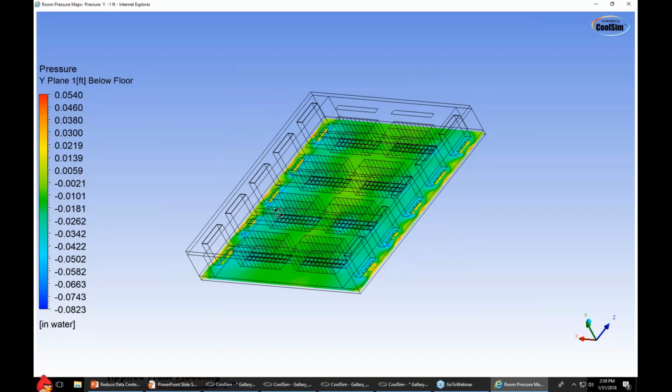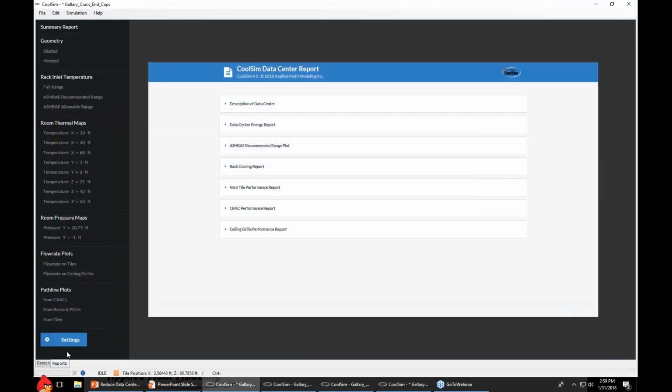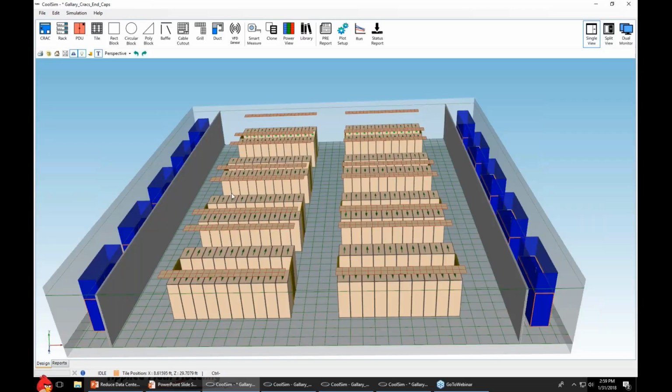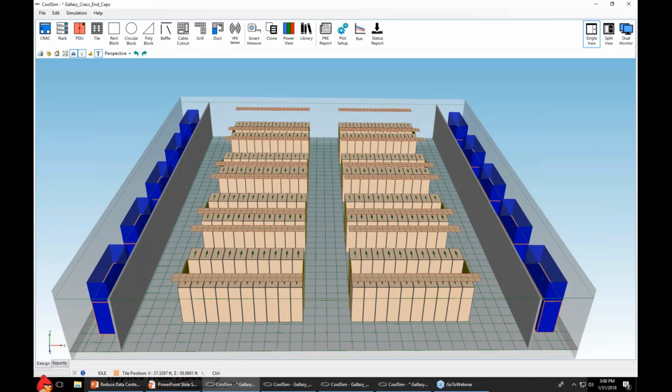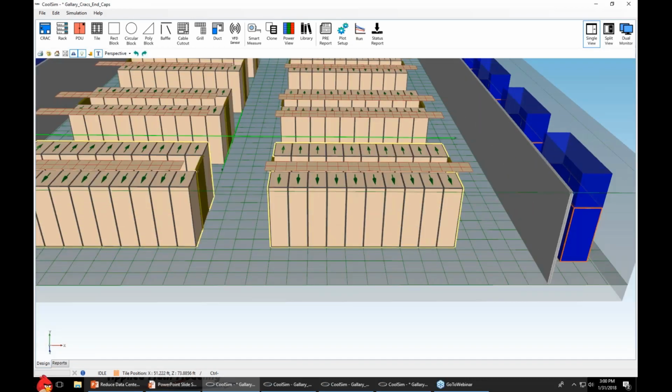Okay, how do you measure the airflow of each rack? It's difficult to measure the airflow of each rack. None of us really know. This comes up a lot in TC9.9 when we meet and talk about this. You have to make some assumptions. Specifically, the rack itself, or the server which is in the rack, and you can in CoolSim create individual servers if you want.